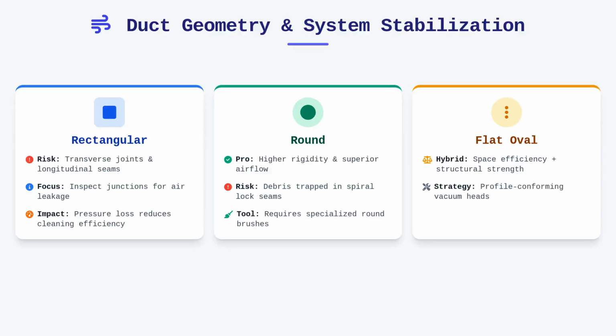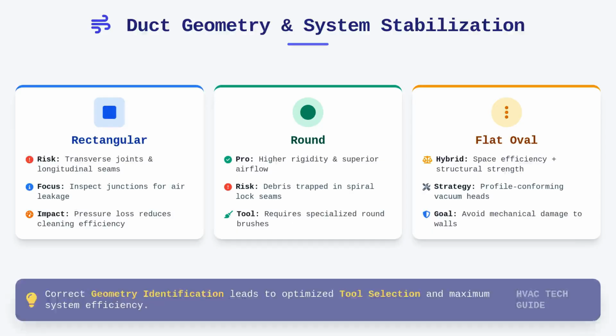Flat oval ducts provide a compromise between the space efficiency of rectangular systems and the structural advantages of round shapes. Identifying these configurations helps you select specialized tools, such as round brushes or specific vacuum heads, that conform to the duct profile without causing mechanical damage.